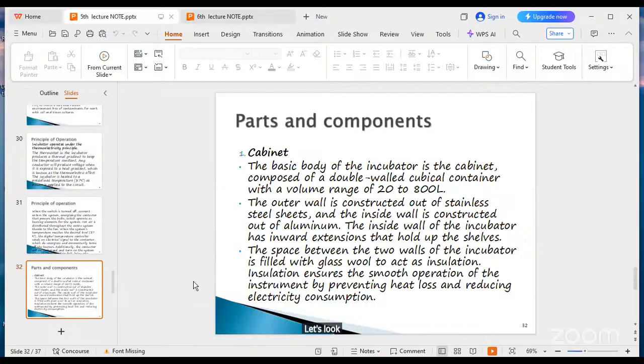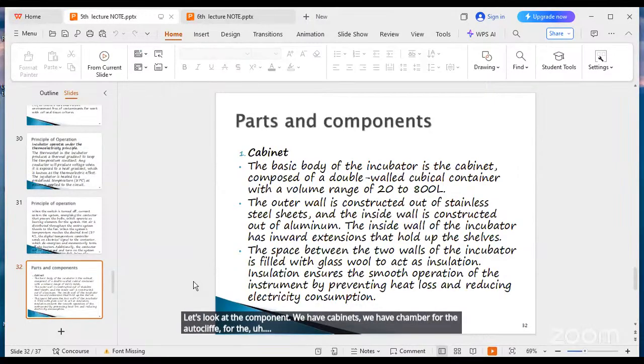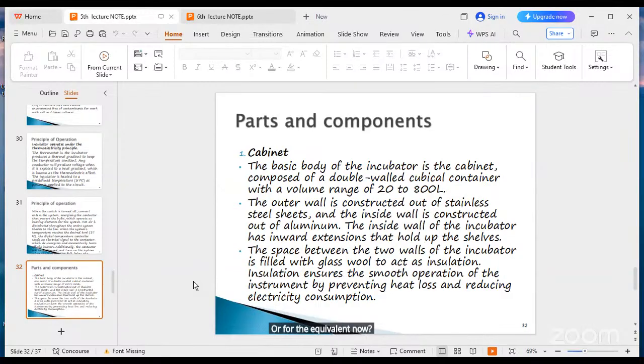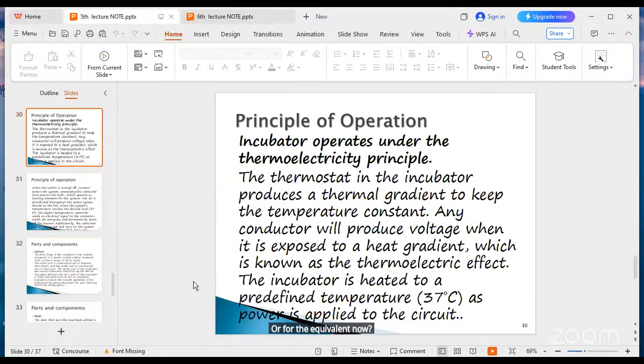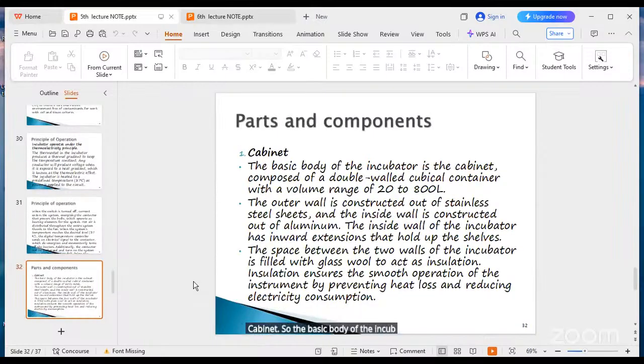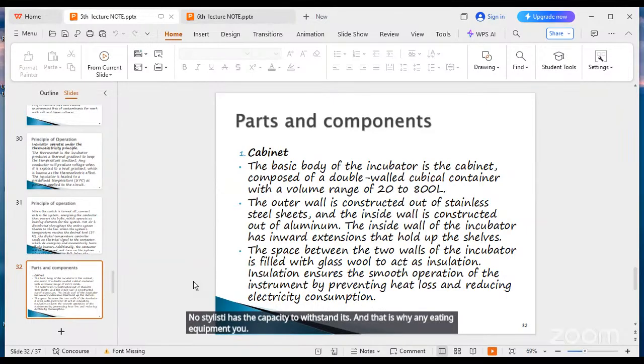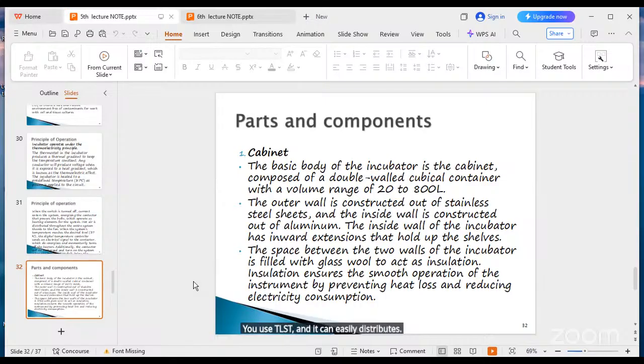Let's look at the components. We have the cabinet, we have the chamber for the autoclave, and for the incubator now we have the cabinet. So the basic body of the incubator is the cabinet, which is composed of a double-walled cubical container with a volume ranging from 20 to 300 liters, depending on the size. The outer wall is constructed out of stainless steel. Stainless steel has the capacity to withstand heat, and that is why for any heating equipment you use stainless steel, and heat can easily distribute through it. And the inside wall is constructed of aluminum.